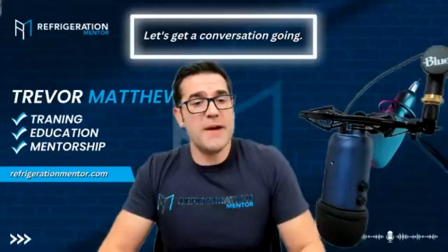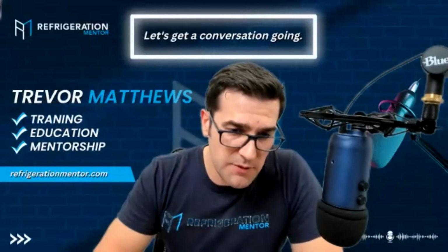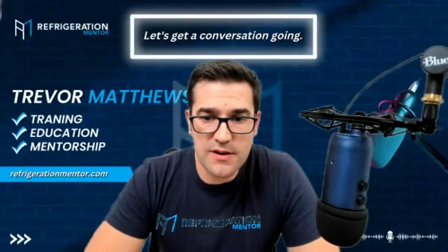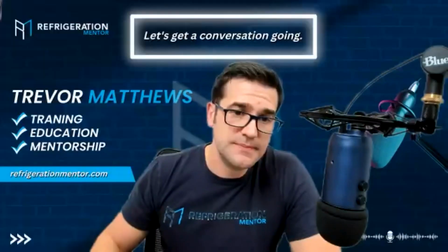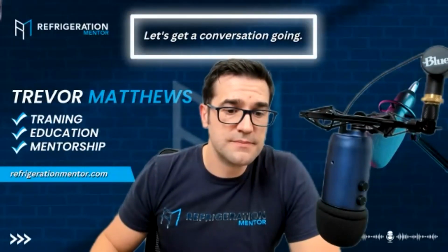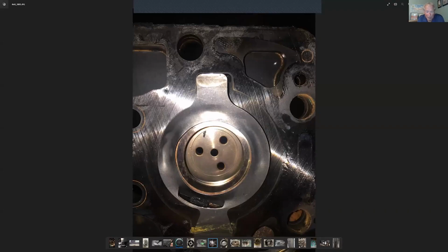But yeah, so there's lots of different things for floodback. What's another one? So we talked about overheat. We talked about floodback. What's another mechanical issue? About flooded starts. Yeah, that lead to slugging. I think that can bring her down in some cases fairly quick, or cause some much quicker damage.